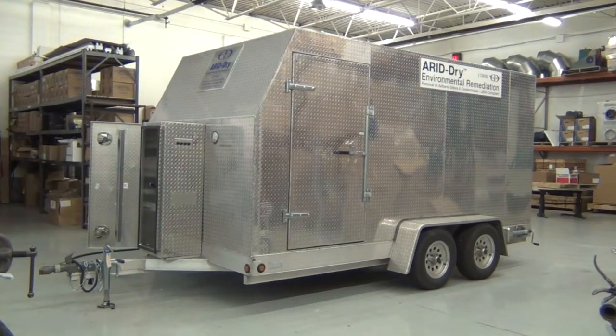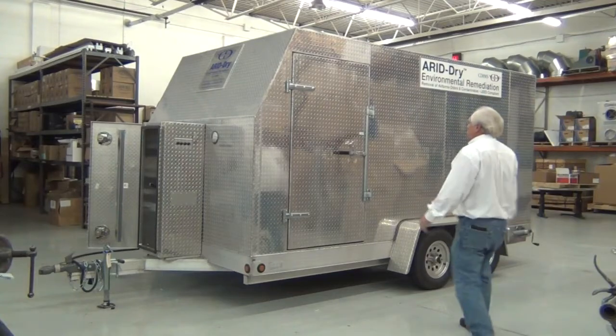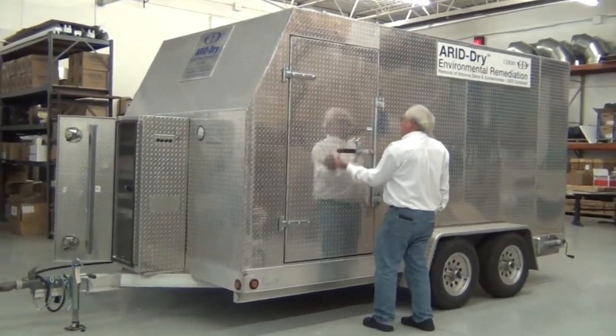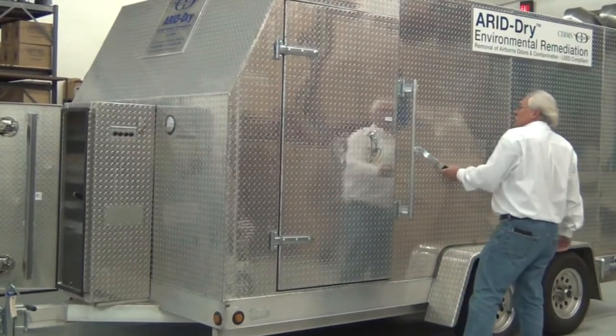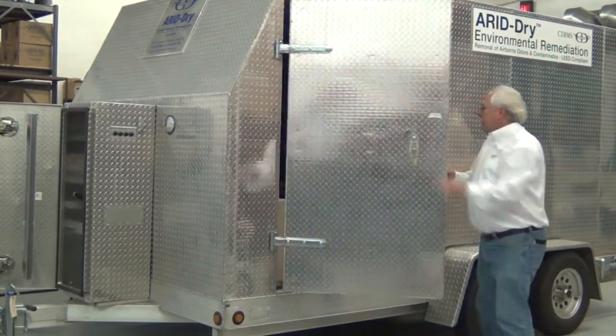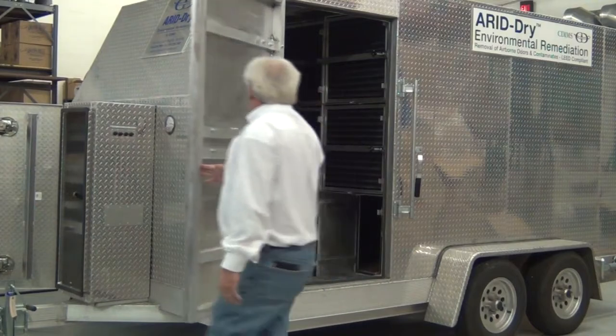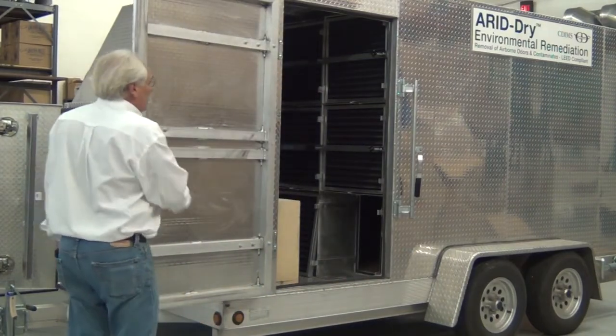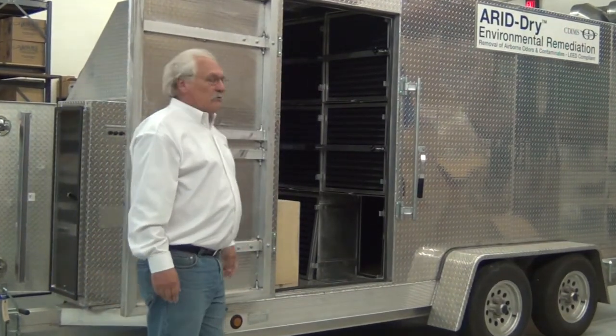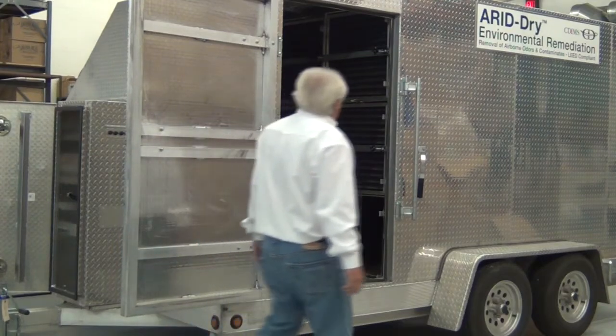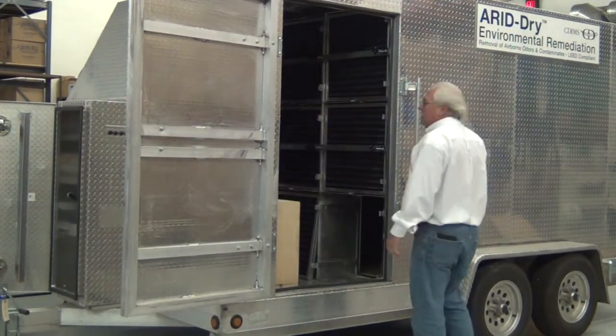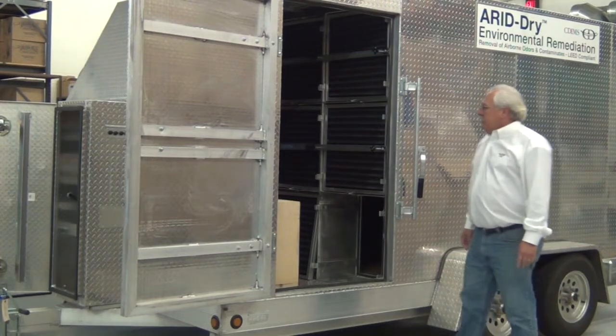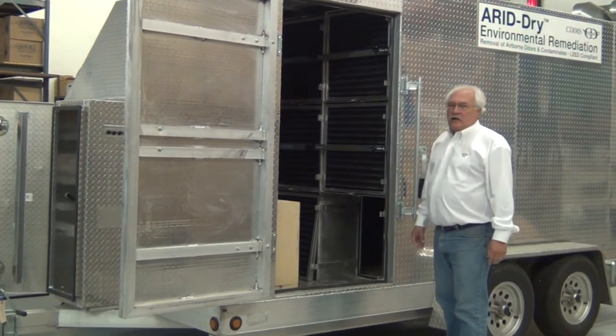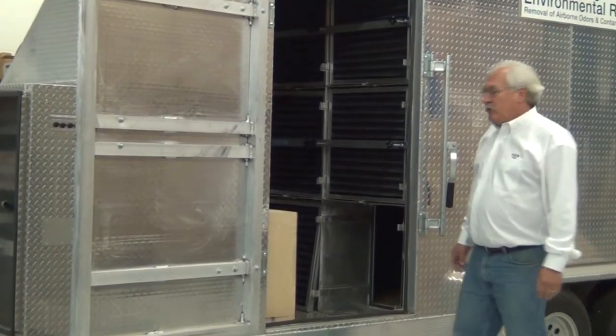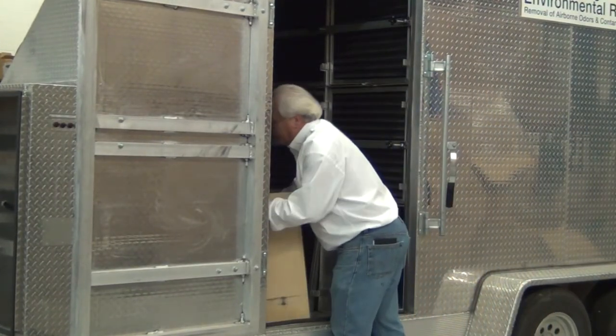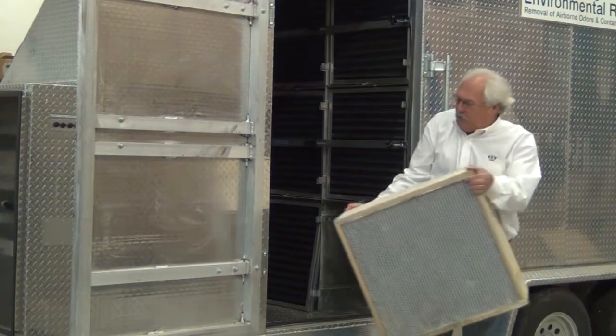The forward access door is located on the driver's side. Opening the door with the latch provides access to the pre-filter and HEPA filter section. The unit has 9 24 by 24 pre-filters, which are a washable MERV 13 filter, and they're followed by a box-style HEPA filter, which is 99.97% effective. This is the HEPA filter.